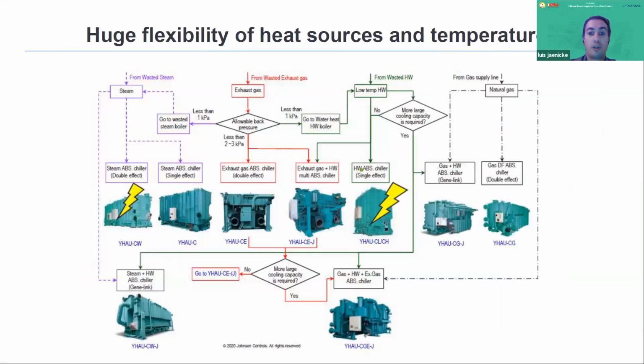Within the Johnson Controls absorption chiller portfolio, there is a huge flexibility of heat sources and temperatures, so we can adapt these absorption chillers to the power generation equipment. If we are using gas engines or gas turbines, we can have direct exhaust absorption chillers. We can also drive the absorption chiller with steam, for example, in the case of a large gas turbine that has an HRSG or steam boiler. We can also drive an absorption chiller with low temperature hot water at around 75 to 80 degrees, so very low temperature hot water can also be recovered to produce cooling. And very interestingly, we can combine different heat sources in the absorption chiller. So we can have a single chiller that takes exhaust gas plus hot water, or steam plus hot water. That definitely simplifies the design and minimizes the number of chillers and the footprint of the cogeneration plant.